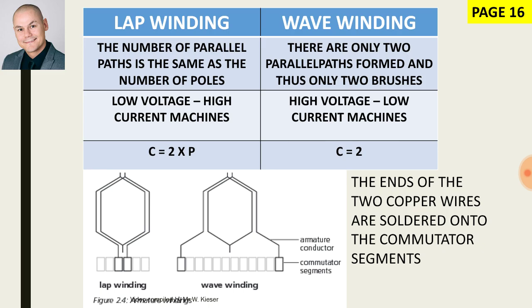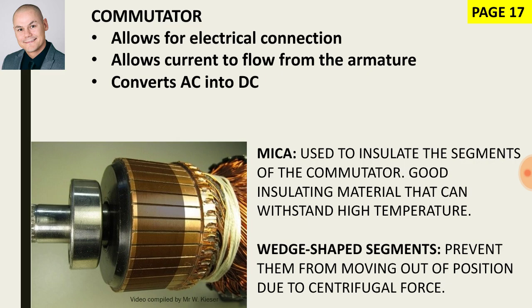The ends of the windings are soldered onto the commutator segments. The main function of the commutator is to allow for electrical connection and allows current to flow from the armature. It also converts AC into DC. The commutator is divided up into many segments made of copper, and each segment is insulated by a material called mica. Mica is a good insulating material and can withstand high temperature.